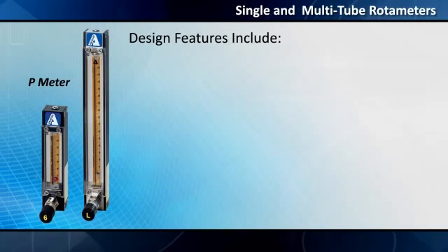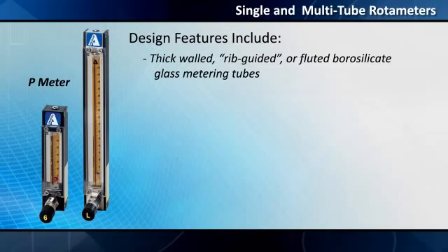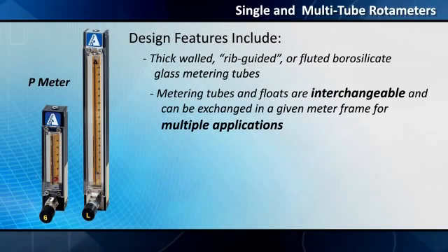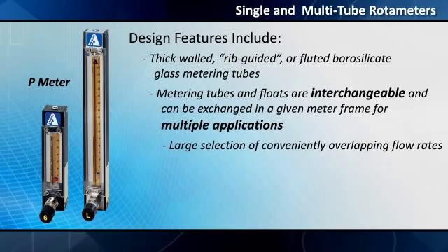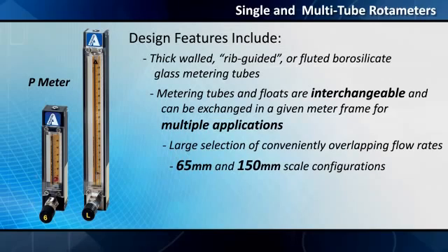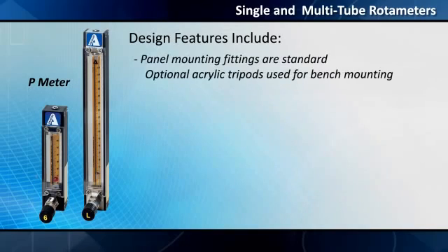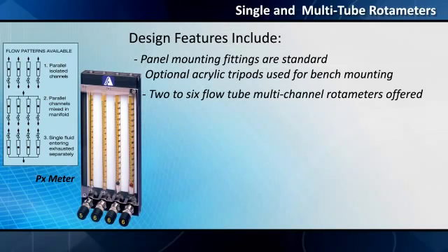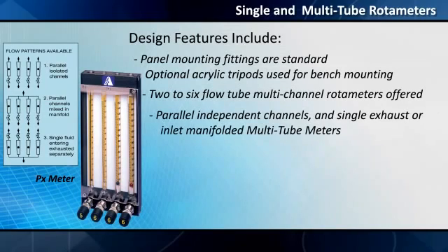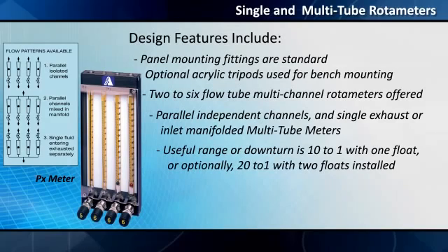Design features include thick-walled, rib-guided, or fluted borosilicate glass metering tubes. Metering tubes and floats are interchangeable and can be exchanged in a given meter frame for multiple applications. Large selection of conveniently overlapping flow rates. 65 mm and 150 mm scale configurations. Extensive list of available direct reading scales for many different fluids. Panel mounting fittings are standard. Optional acrylic tripods used for bench mounting. 2 to 6 flow tube multi-channel rotometers offered, with parallel independent channels and single exhaust or inlet manifolded multi-tube meters. Useful range or turndown is 10 to 1 with one float, or optionally 20 to 1 with two floats installed.